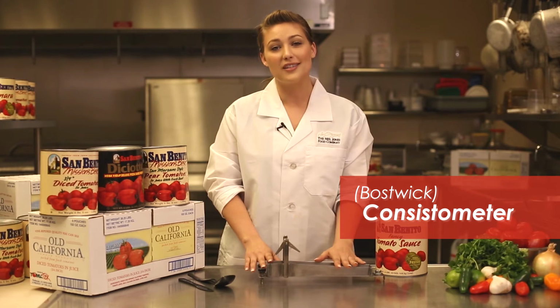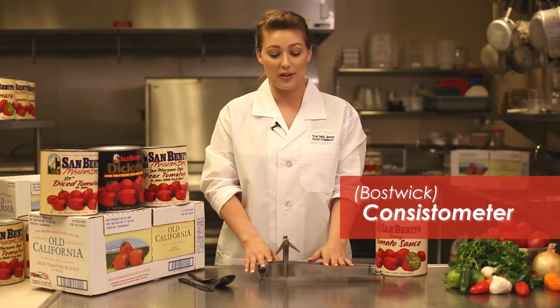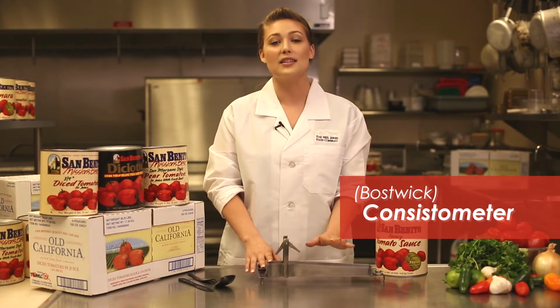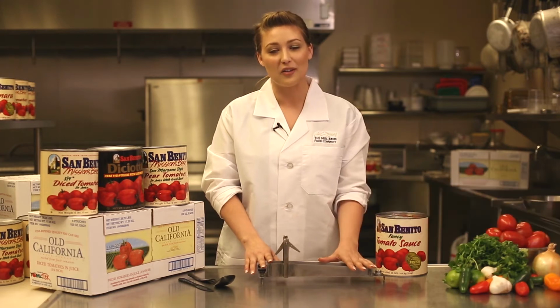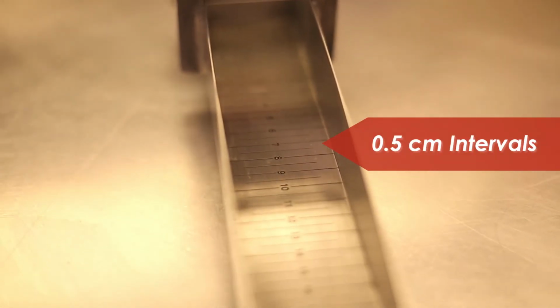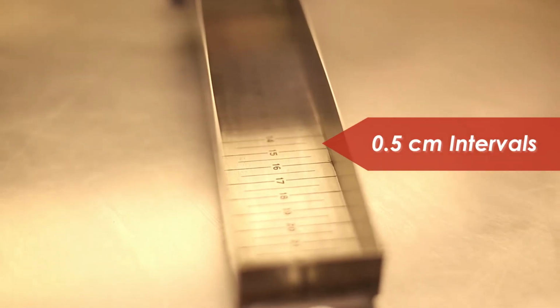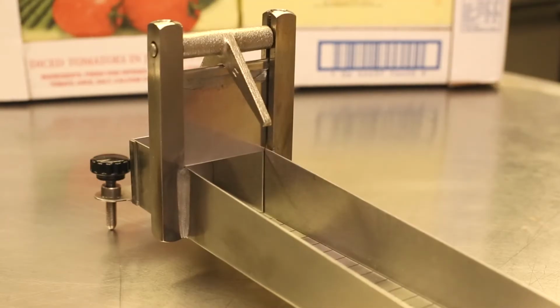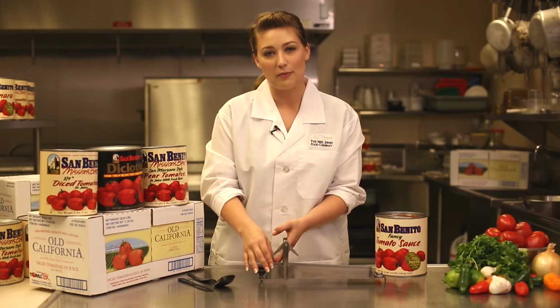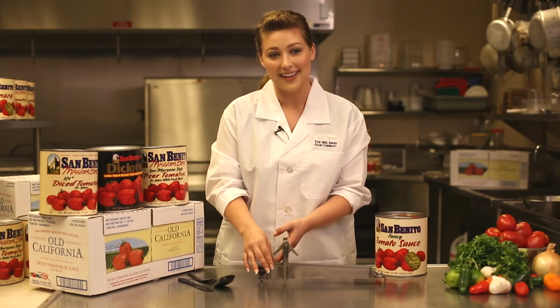It's a low-cost, durable stainless steel instrument that uses very little space, but it's the simplest, most accurate way of conducting a flow test. The unit is engraved with a series of graduations at 0.5 centimeter intervals all along the bottom of the trough, which is separated near one end by a spring-loaded gate. This creates the chamber where the sample being loaded will be tested.